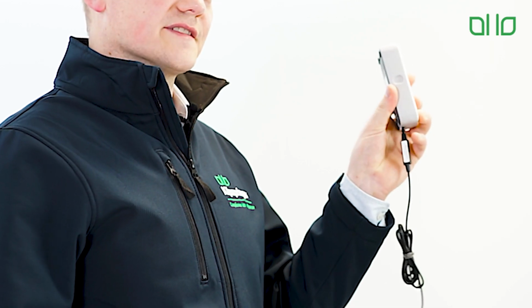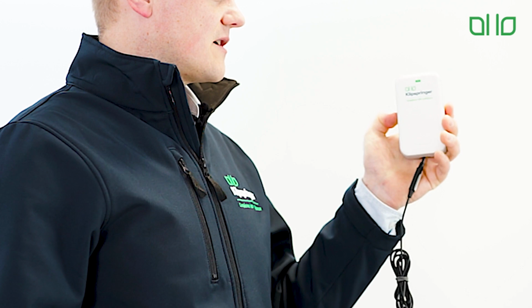Press the button once on the side of the unit. This should give a flash, either one flash or two flashes. If there's no flash at all, this means the unit is completely dead. That's either a battery or it could have had water ingress.